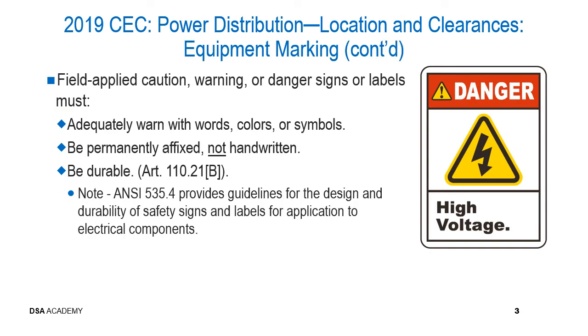Whenever equipment markings are field applied, the caution, warning, or the danger signs or labels that are field applied must adequately warn with words, colors, or symbols. They're required to be permanently affixed and not handwritten. They are also required to be durable, and the requirements are identified in California Electrical Code Article 110.21(B). An example of a simple equipment warning sign that can be field applied is shown on the right hand side, where they're actually showing words and symbols and obviously identifying that there is danger and high voltage.